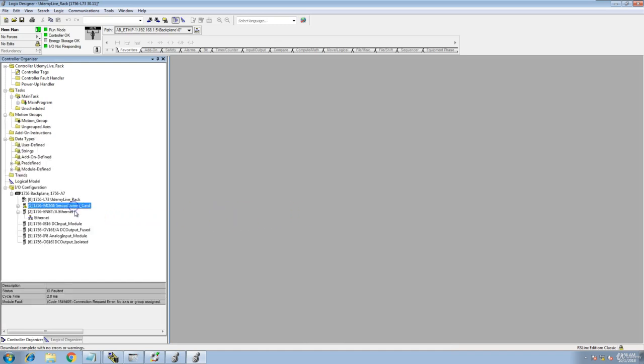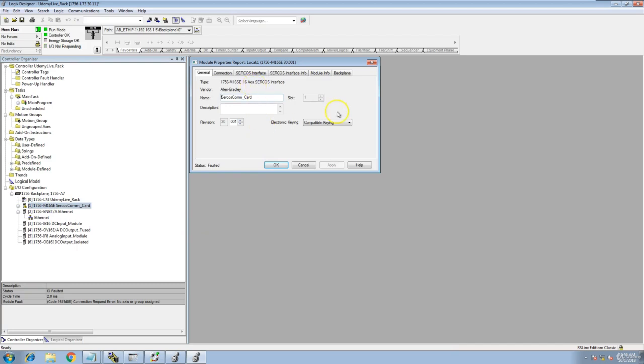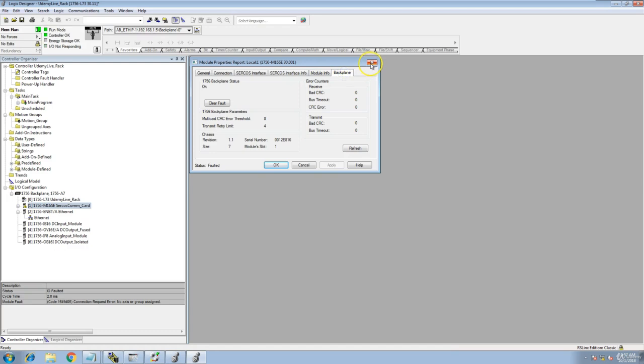The reason they don't do this with Sercos is because they do not have the ability to auto detect if you have a motion group assigned or not. So this says there's no axis or motion group. So we still have to add a motion group in here.